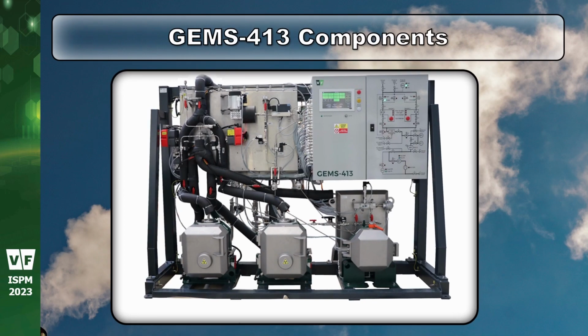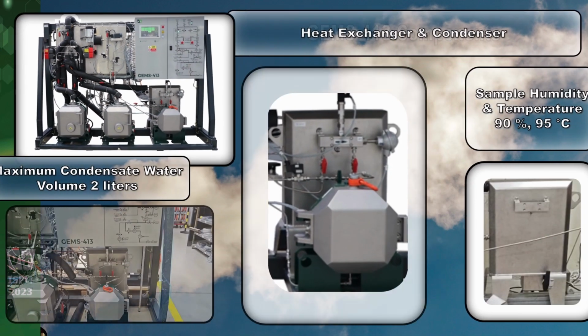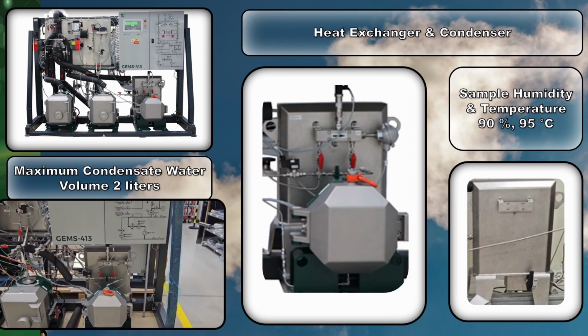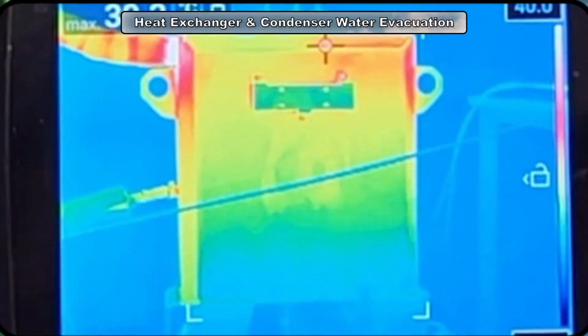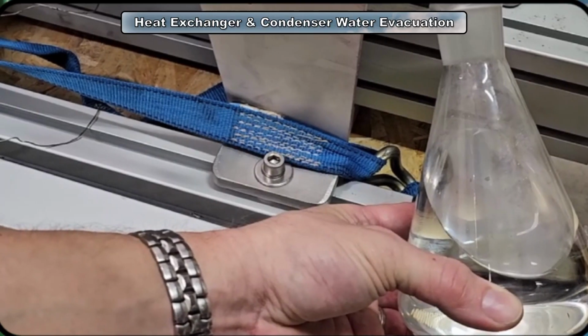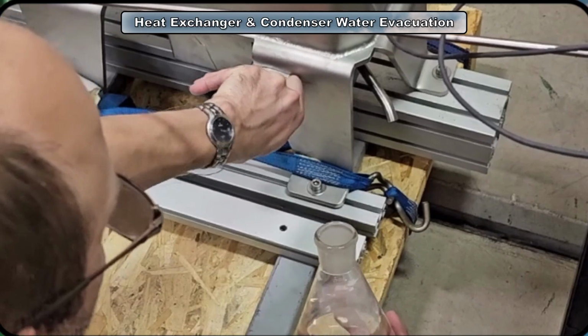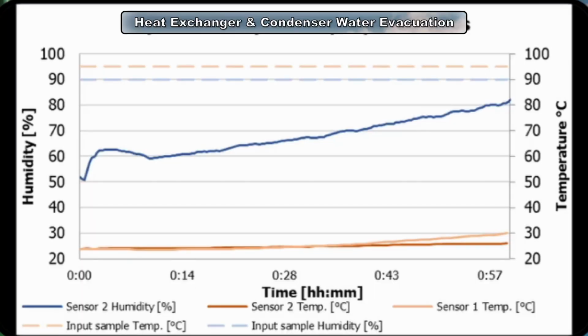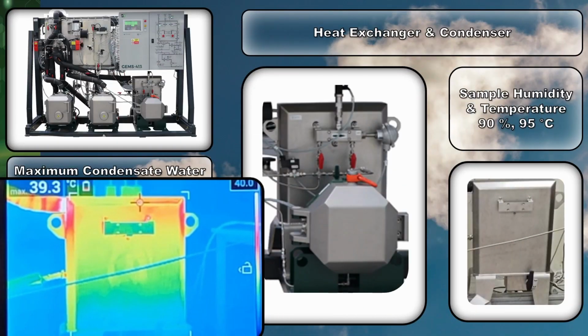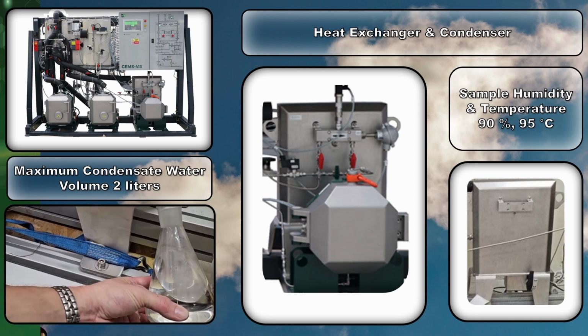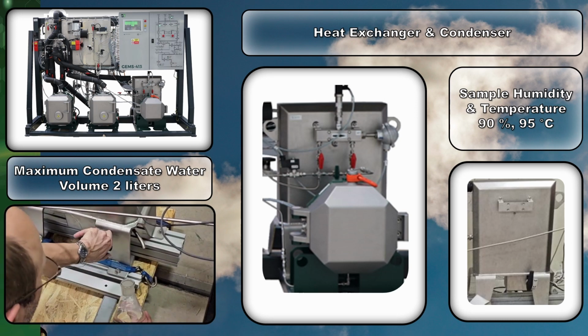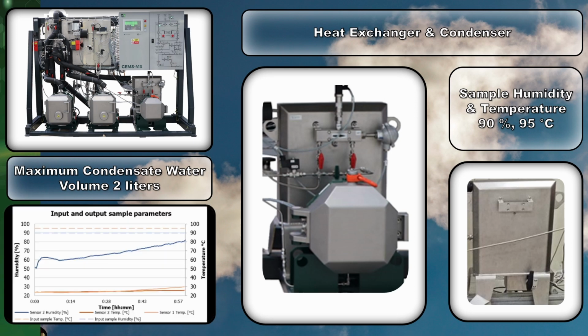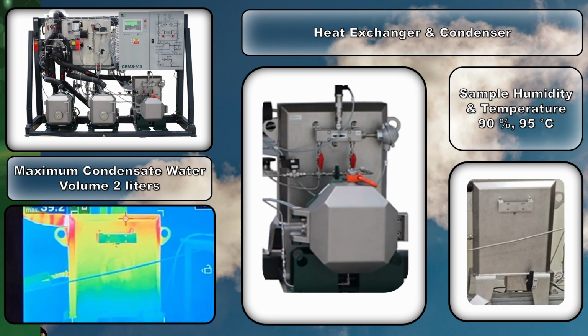The saturated harsh condition air sample with a maximum temperature of 95 degrees Celsius must be cooled down. The temperature and humidity are reduced to 50 degrees Celsius and 90% relative humidity in the heat exchanger and condenser. Condensed water is collected. The process of condensed water removal is shown on video. Maximum volume of condensed water is 2 liters.